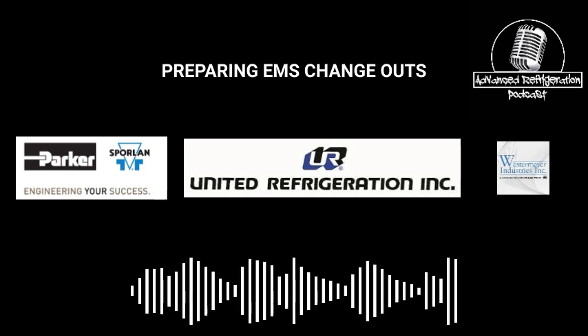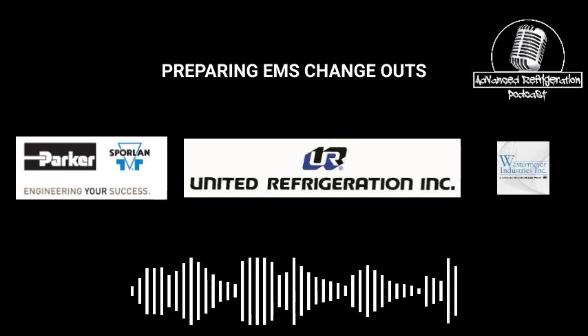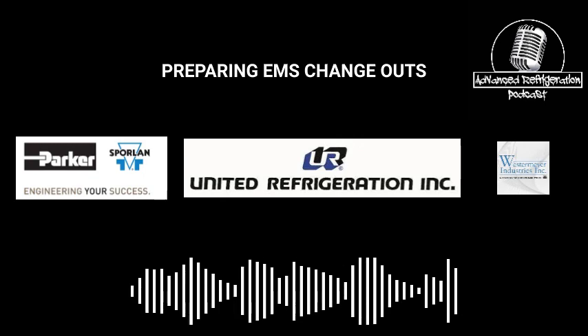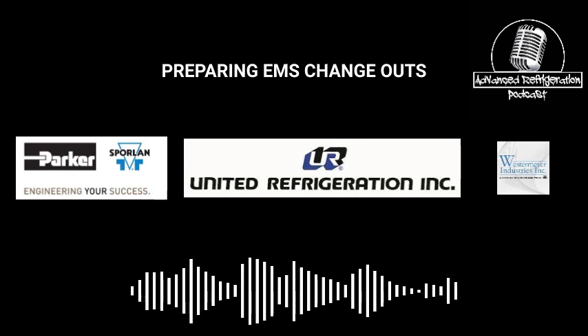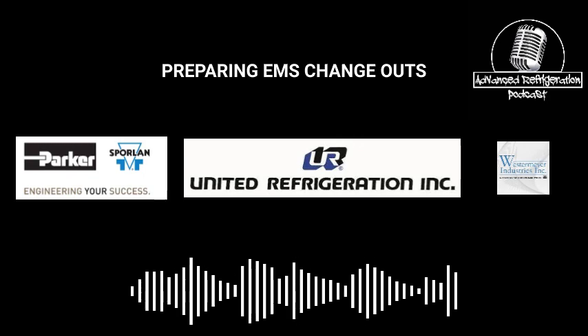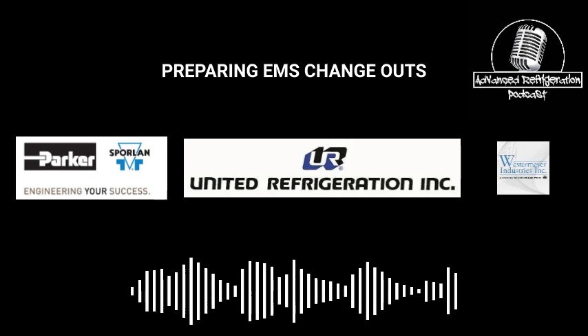Now with Danfoss, make sure if you're going to do this, you take the time. I'm doing a job right now and I'm slowly starting to do it. I'll put the relay states. If it's normally open, normally closed, you need to put that on there because Danfoss doesn't have fail-safe switches. So you got to put that relay state on there, whether it's normally open or normally closed. That's a big thing. If somebody has to reprogram this, or if they're trying to troubleshoot it, they're trying to know what it does. That's a huge thing.